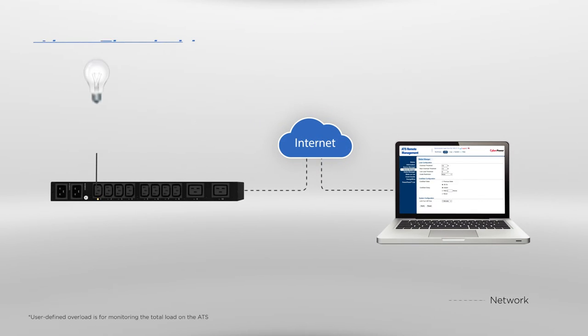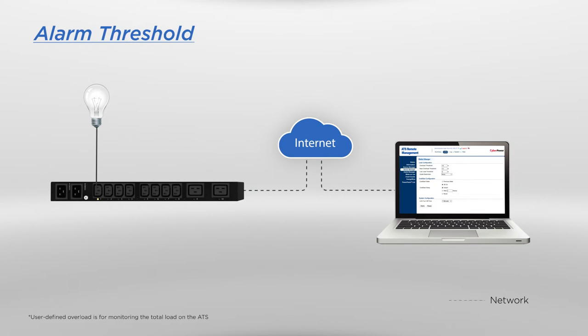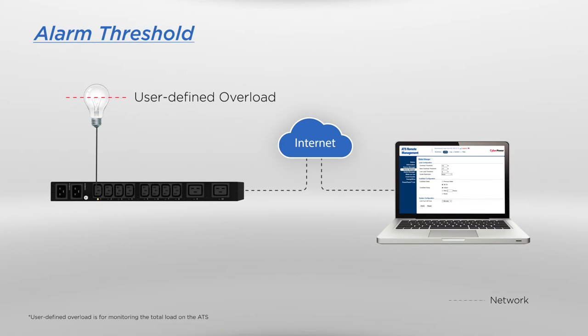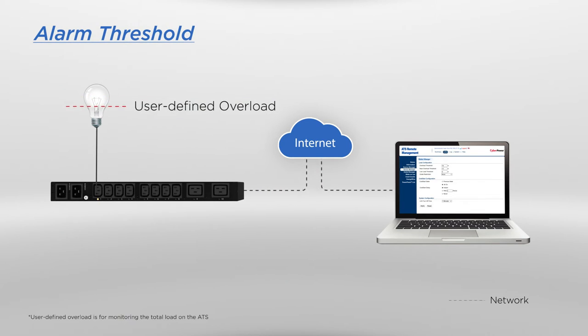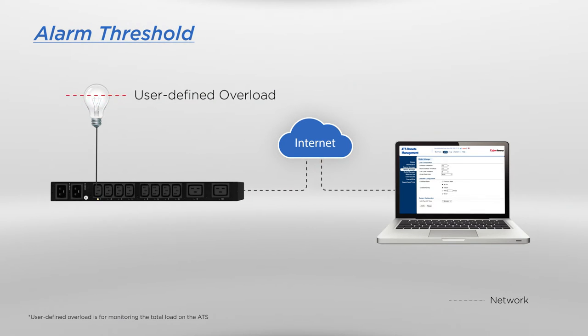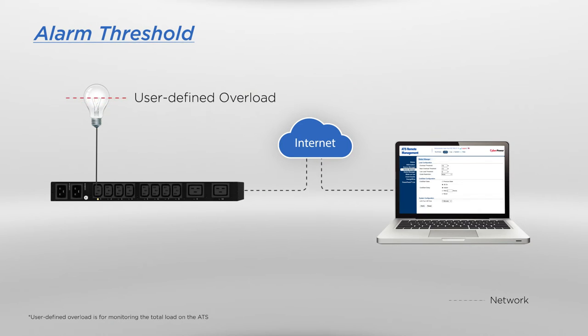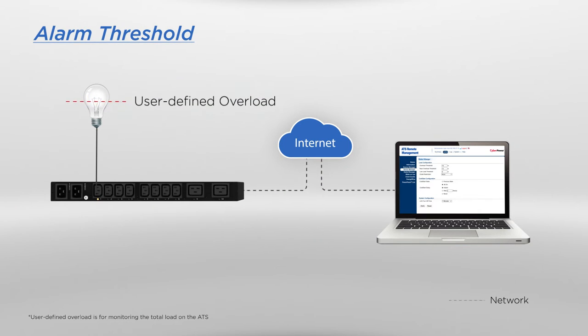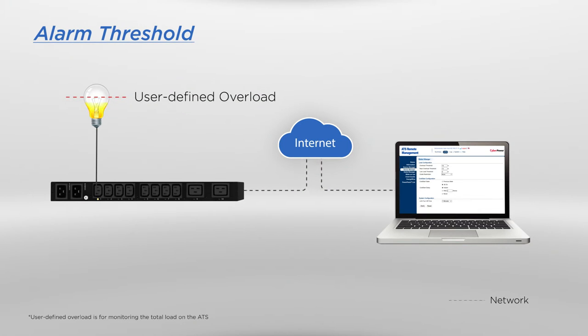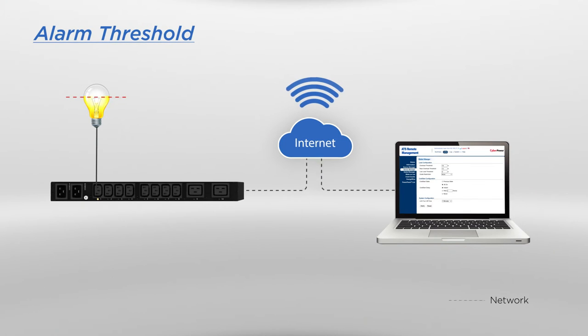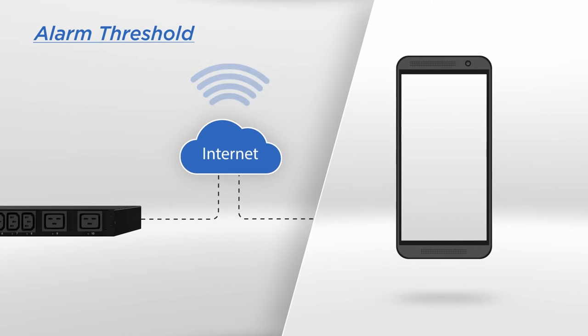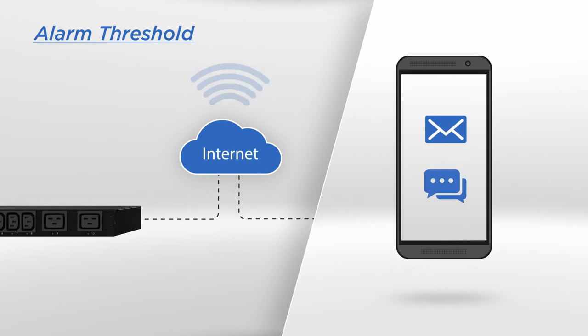To provide advanced power protection, the ATS is designed with alarm threshold that enables you to set up current values for overload warning over the network. Once the total current on the ATS exceeds the set value, you will be informed by automatic notifications such as email or SMS.